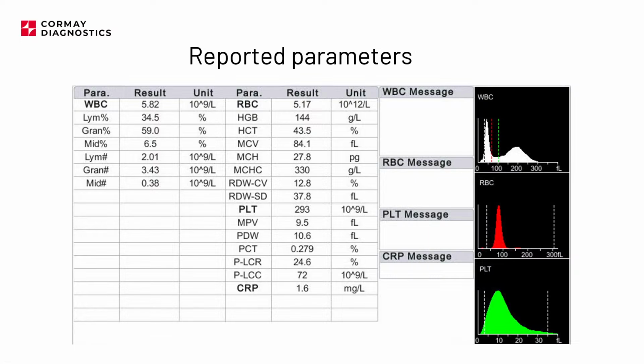And we also have the CRP parameter reported by the analyzer. Since there is a separate WBC chamber and RBC chamber, with PLT being a part of the RBC, and as I said, CRP is a separate one. On the screen of the analyzer, we can also see some messages. Those will be areas where flags related to the appearance of the histogram, or to the level of those parameters, will appear.